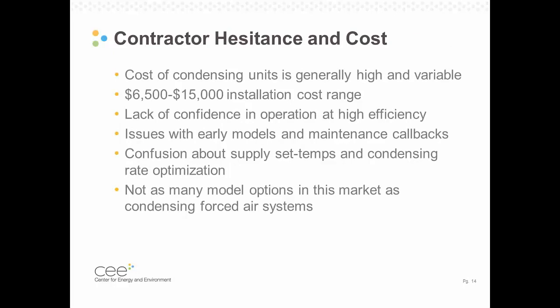A little bit more on some of the anecdotal evidence on contractor hesitance and cost. The cost of the condensing unit is generally higher and variable. We would see bids between $6,500 and $15,000 for an installation of a condensing boiler, and we wanted to look at why that range was so large, as well as the top end of that range being so high. There tended to be a lack of confidence in the operation at high efficiency, so how often these systems were condensing was a big question. And then there were definitely some issues with some earlier models of condensing boilers that produced a lot of maintenance callbacks and system failures that a lot of contractors had cited as a concern. There tended to be a little bit of confusion about the supply set temperature and condensation rate, and so we wanted to explore that impact as well. And then we also noticed that there weren't as many model options in the market as their condensing forced air counterparts.